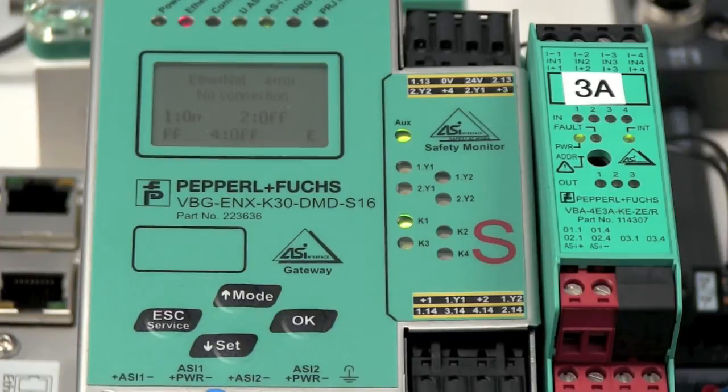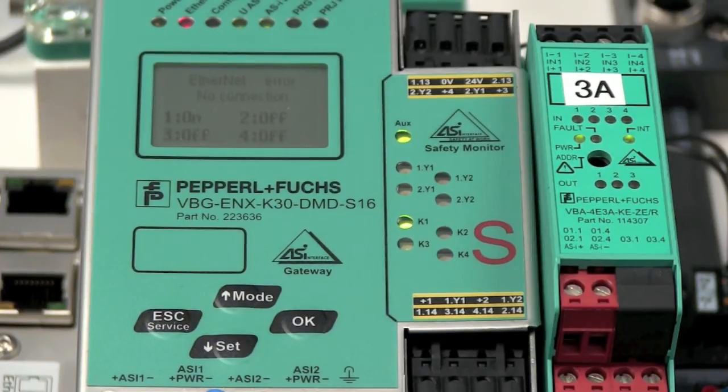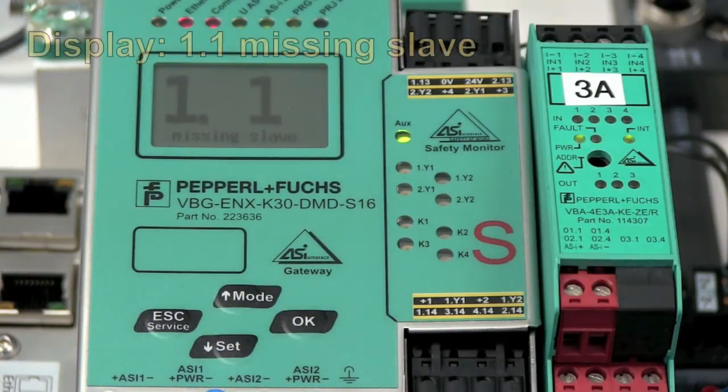Let's work with a K30 gateway with integrated safety controller. Currently, as you can see by the green K1 LED, OSSD1 is in the release state. I will again simulate a fault by simply removing the e-stop from the network. This will make the safety contacts drop out.